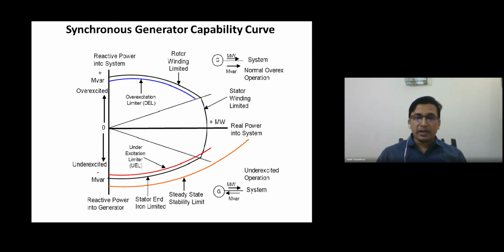And what will happen if over excitation is given? Your rotor coil will be heated, your generator life will be damaged. It will be less, it will be a wear and tear situation from over excitation. It will put impact on rotor windings.